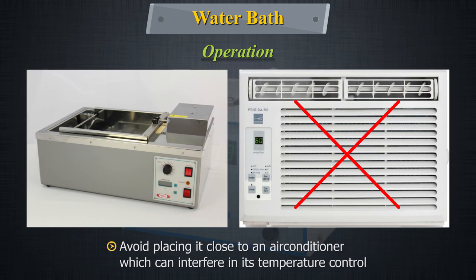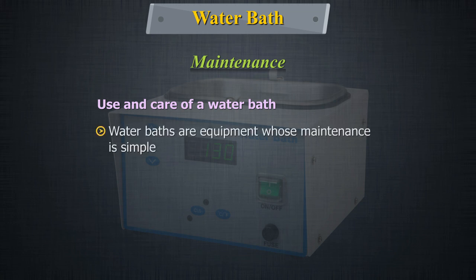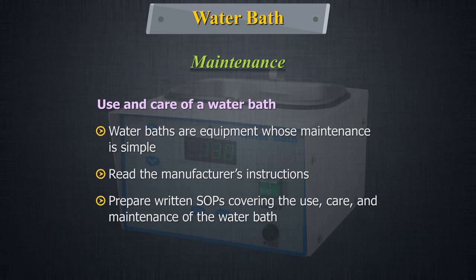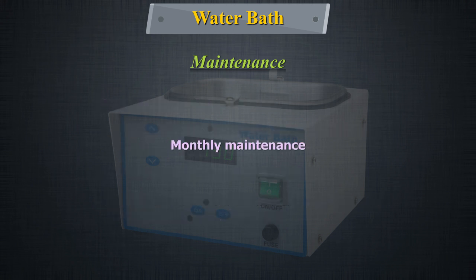Avoid placing it close to an air conditioner which can interfere in its temperature control. For maintenance and use and care of a water bath: water baths are equipment whose maintenance is simple. Read the manufacturer's instructions. Prepare written SOPs covering the use, care and maintenance of the water bath. The most common routines are outlined below.